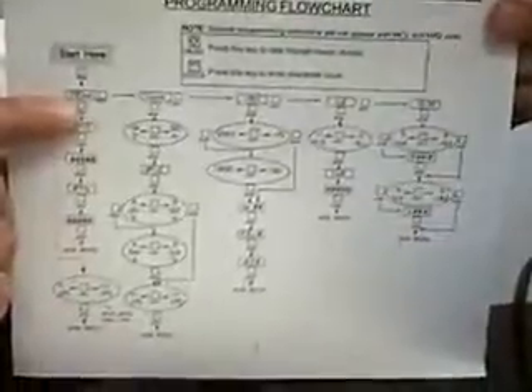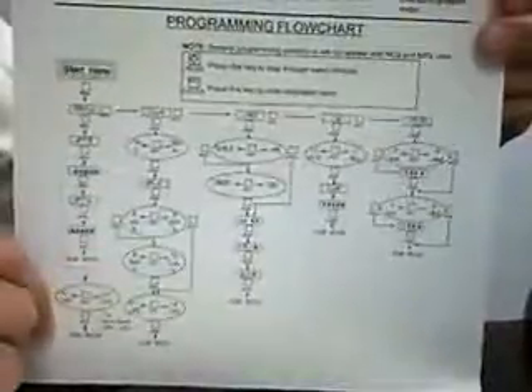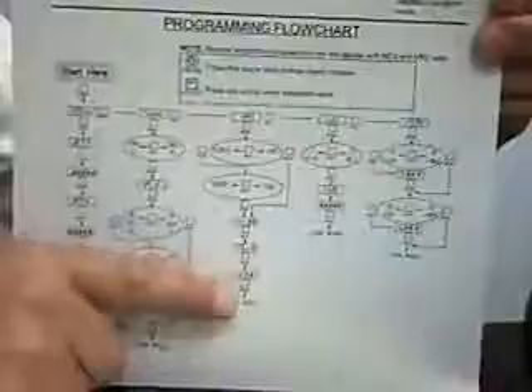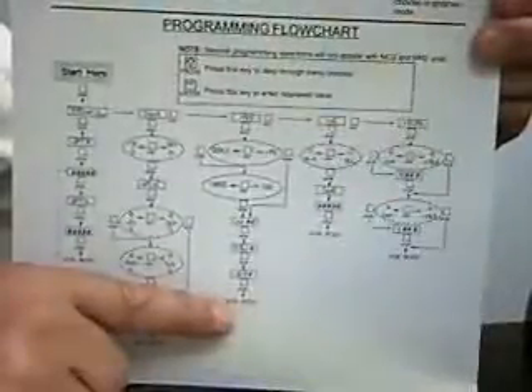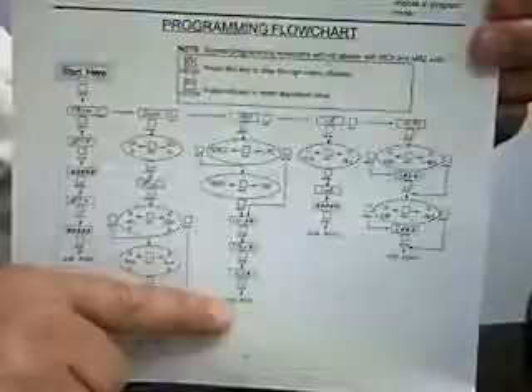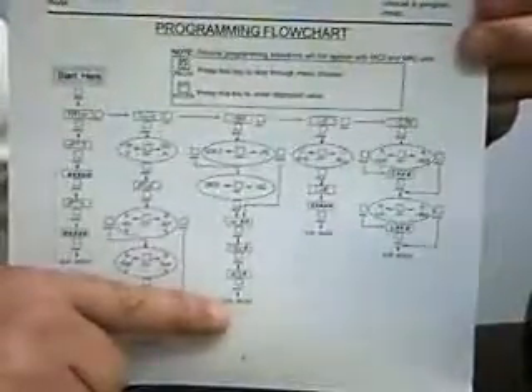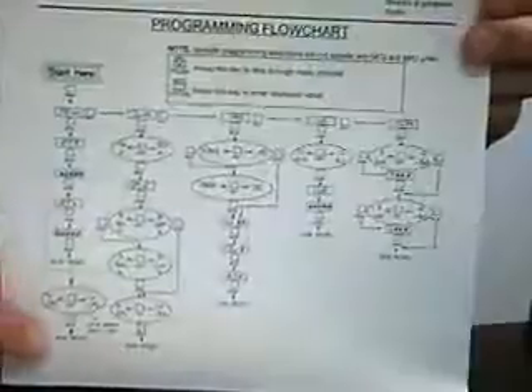You'll notice first that pressing the program button brings you to the first menu group, which in this case is for the group called Factor. Pressing the program button again moves you to the next menu group, and so on. Once you're at a particular menu group of interest, pressing the Enter button brings you into that group. Finally, when you complete a group, it returns to the Run mode. Often, it's advisable before entering into the setup mode to display the flow rate, because then you'll have the indication of an R in the far left-hand side to tell you've returned to the Run mode. We'll be entering each menu group, configuring it, and then returning to the Run mode before moving in again to the next menu group.